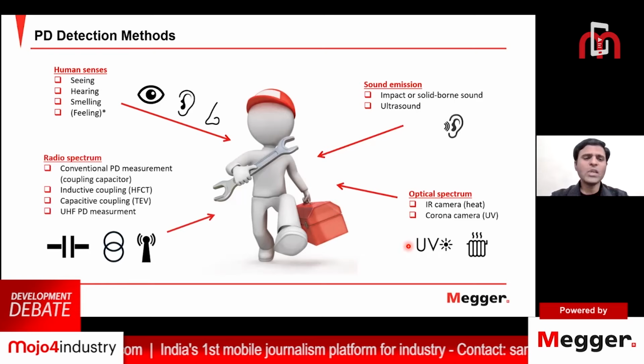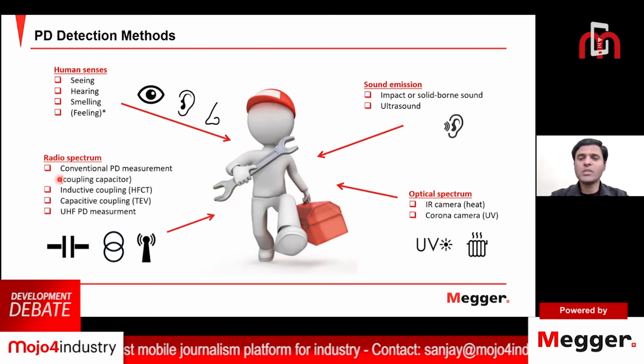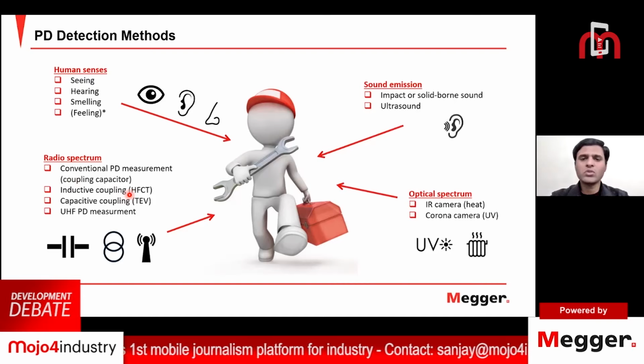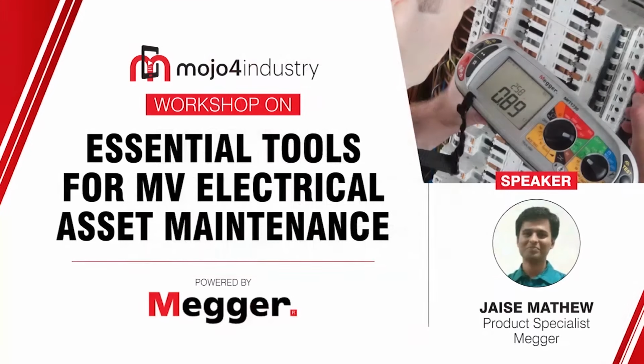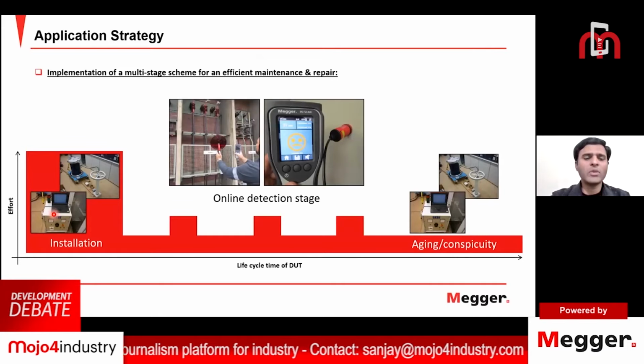In the radio spectrum, conventionally PD measurements are done with the help of a coupling capacitor, as per the standard regulations on how the testing methods have to be done. However, inductive coupling can be done with the help of high frequency current transformers. Capacitive coupling can be done using transient earth voltage sensors on the switchgear panels, and ultra high frequency PD measurements are also recommended to identify PD activity in electrical assets in the utility. So different characteristics of PD need different types of sensors to identify them. So when to do which, there is a strategic manner for the maintenance.